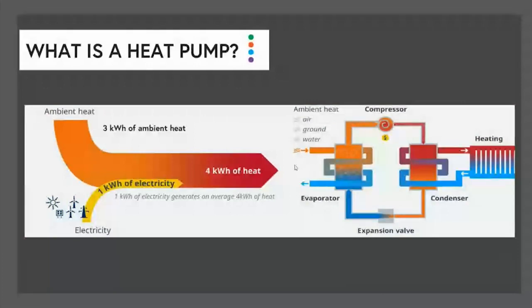What do we have? We've got the electrical grid supplying 1 kilowatt hour of electricity. What that's used for is the heat pump to function. So the appliance uses electricity to run the compressor and the pumps and all the bits on it, and that translates into heat that's generated for the system. But what's in the heat pump is refrigerant, and that refrigerant is able to absorb heat from the atmosphere, and that is then combined with the electrical input to create the total amount of heat generated to the system.